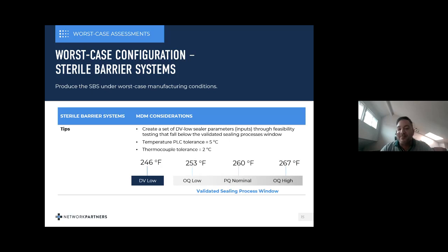That's a tricky one. I've got to think about that one. If you go into the standard, TS 16775, it really gives you a lot of guidance on protective packaging. So let's say tip protectors. Let's take that for instance. If you're packaging blades or sharp medical devices, that's part of what you're going to be selling to the end user, right? So you want to make sure it's reflective of that. So I would use those.